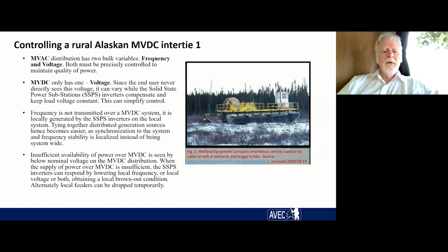If you have insufficient availability of power in an MVDC system, the voltage drops. If you have a surplus of renewables, you can push power back into the line and raise the voltage. If the voltage starts to go high, then high-cost sources of power like diesel generators can back off. This is all done without any fancy communication system, just based on the voltage you see on the line.